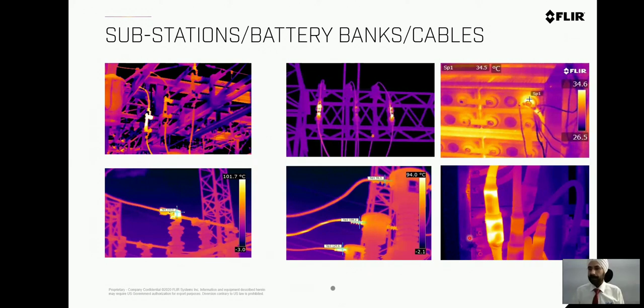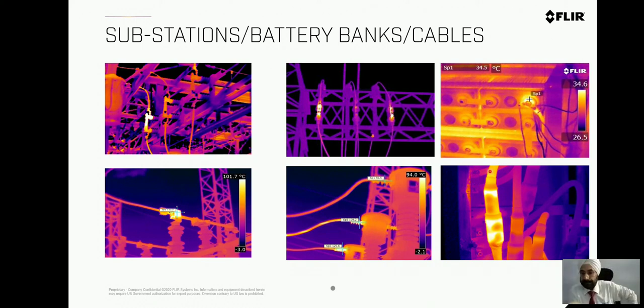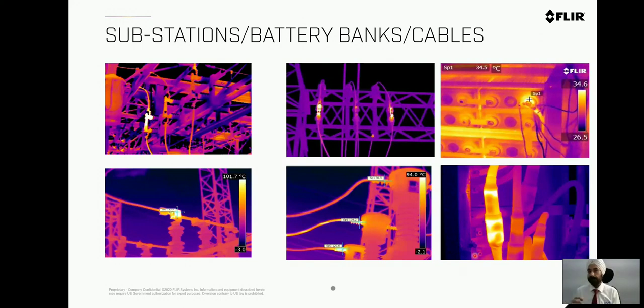In additional images, entering a substation allows you to see where the heat is within two seconds. CTs, the exact temperature of the CT bushing, battery banks — all are critical utility applications. Cable joints are very difficult to inspect once sealed and heat-shrunk, but with thermal imaging, all joints emitting less radiation are visible as okay while one joint showing higher temperature clearly indicates something is wrong. This gives the operator a different perspective — a different eye altogether.